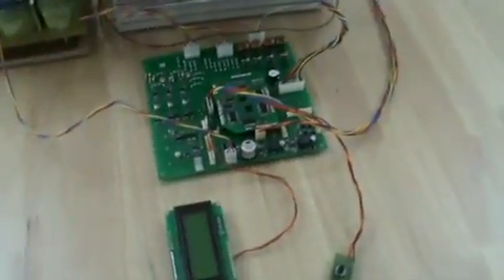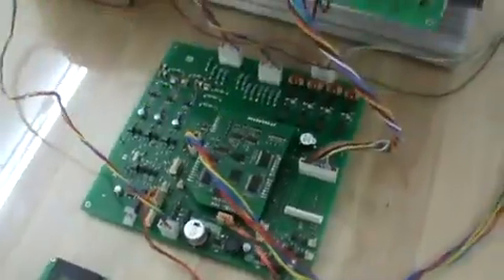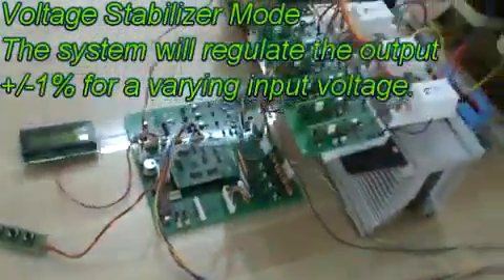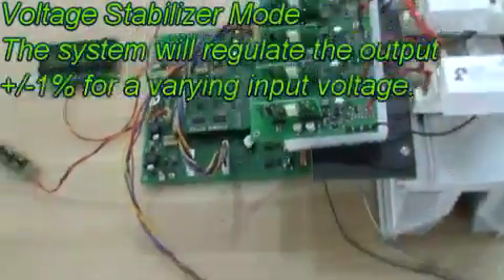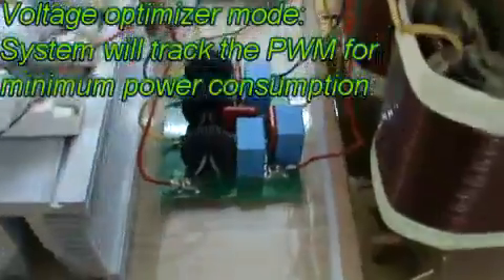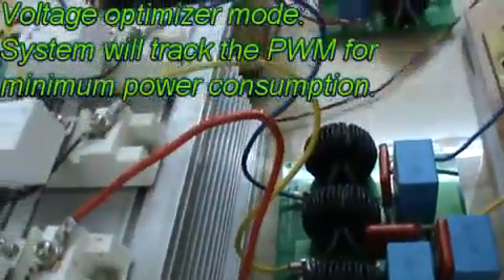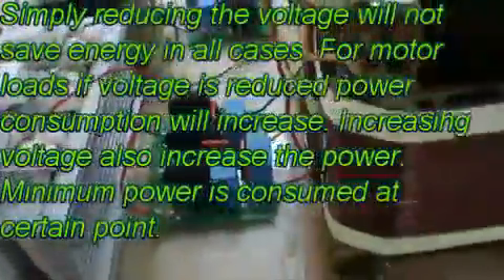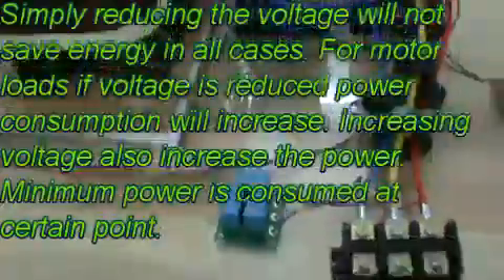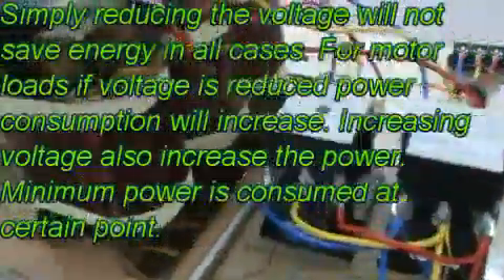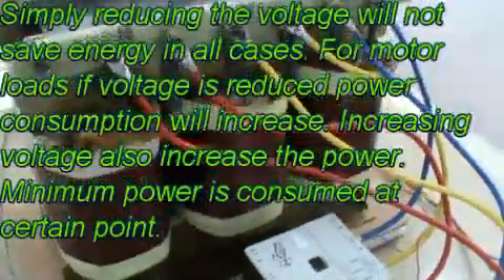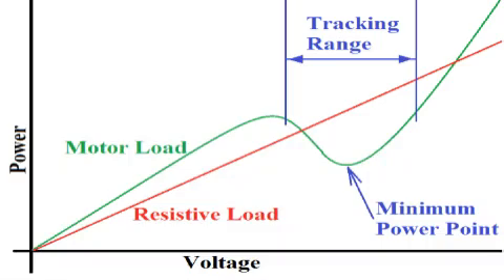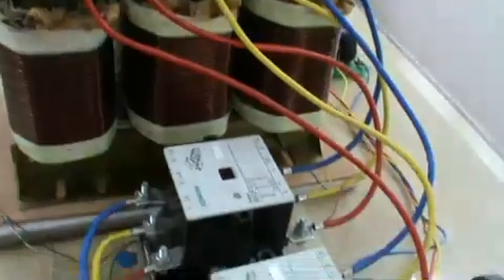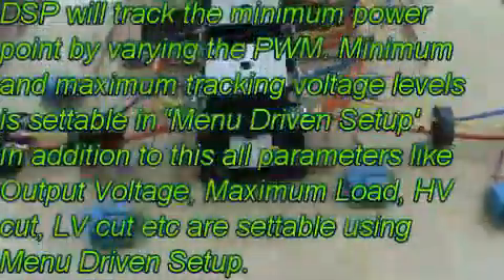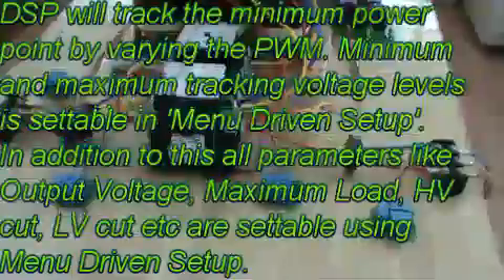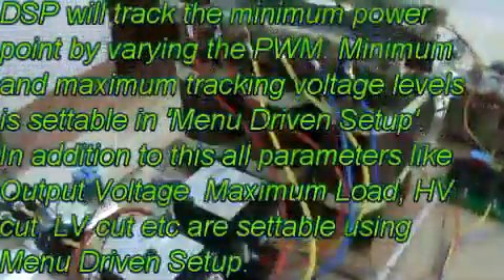There are two modes of operation in this system: voltage stabilizer and voltage optimizer. In voltage stabilizer mode, the system gives plus or minus 1% regulated output for a varying input voltage. In voltage optimizer mode, the system always tracks the voltage at which minimum energy is consumed. Simply reducing the voltage will not save energy in all cases - for a motor load, reducing the voltage will increase power consumption, and increasing the voltage will also increase power consumption. The minimum power consumption occurs at a certain voltage. This graph shows the minimum power consumption point of a motor load. The DSP tracks this point by varying the PWM and maintaining it for minimum power consumption. This minimum and maximum tracking range can be set in the unit, and the voltage will not go beyond this limit.